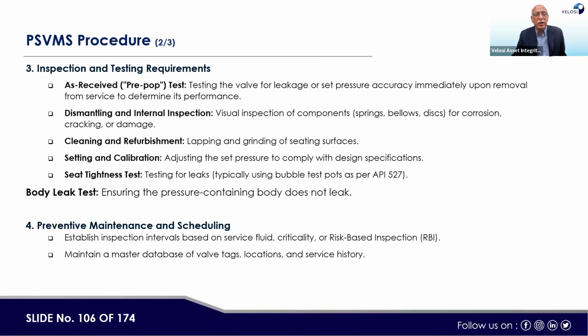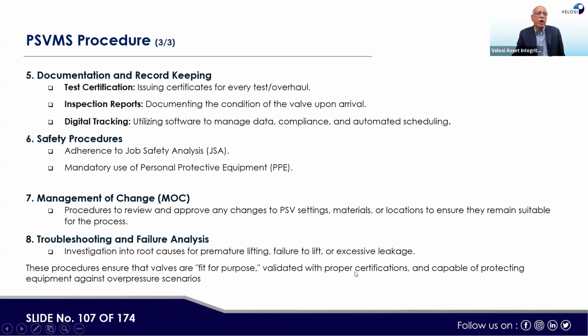Then preventive maintenance and scheduling is also covered under this document. Either a time-based or RBI-based, risk-based, program is followed. Maintain a master database of valve tags, location, and service history. Now, documentation and record keeping: test certificate, inspection report, digital tracking, all are required to be managed properly. Then safety procedure: adhere to job safety analysis, and mandatory use of personal protective equipment while testing the PSVs or removing the PSVs from the plant. Then the management of change process is also covered under this procedure. Troubleshooting and failure analysis is covered, and guidelines are provided in this document.